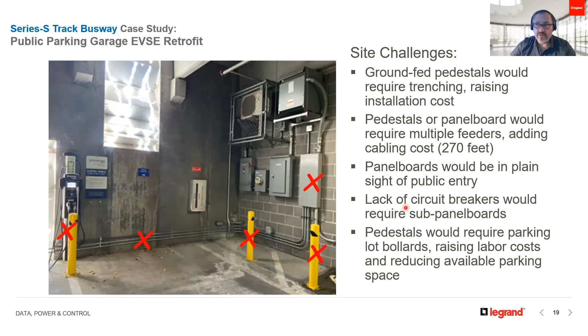So you want to simplify. With this system, they were able to carry only one feeder all the way to the transformer—that's what DTT means, dry type transformer. You can see the feeder right here. So they only needed one feeder, one cable, from beginning to end until the point of use, which made it a lot simpler and faster to do. The whole installation took only a day and a half, which is pretty fast considering the space they were trying to connect. And it didn't have much existing infrastructure to expand from when they started.